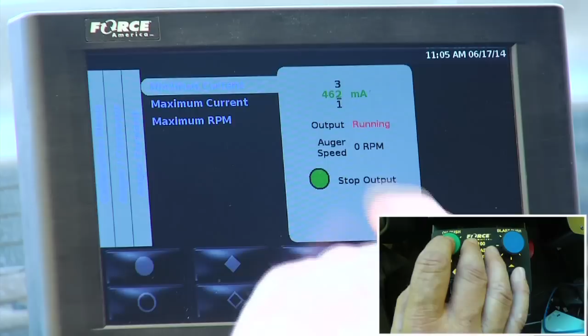If I push the green button, it would run and give me an RPM of 0. What I'm trying to do is min my hydraulics, so it's almost ready to turn the auger but just barely stopped. That's called my min. Here it shows 462 milliamps as the min.